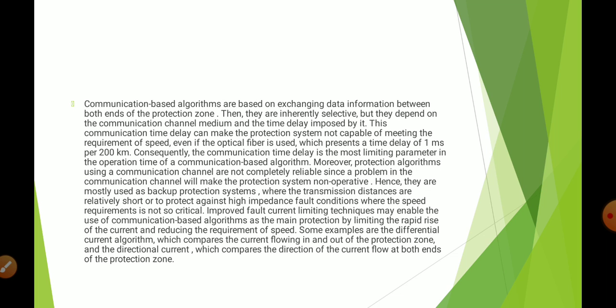Next, the communication based algorithms. They are based on exchanging data information between both ends of the protection zone. Then, they are inherently selective, but they depend on the communication channel medium and the time delay imposed by it. This communication delay can make the protection system not capable of meeting the requirement of speed, even if optical fiber is used, which presents a time delay of 1 millisecond per 200 km. Consequently, the communication time delay is the most limiting parameter in the operation time of a communication based algorithm.